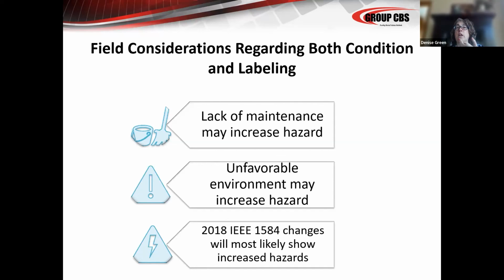So if you feel that you have a substation where your labeling and your values are very high and you're approaching that 40 calorie level, that might be a worthwhile investment to have some of those labels recalculated, so that you're sure that your staff is using the proper tools and the proper PPE to interact with that equipment. So it's not as much of a concern on your end as it is just on a calculation label end. If this is 20 calories and you have your staff wear 40 calorie suits, you're most likely going to be covered. The changes that I've seen in recalculations of labels have not doubled. It goes up the most in shallow 8-inch deep and 12-inch deep cabinets.